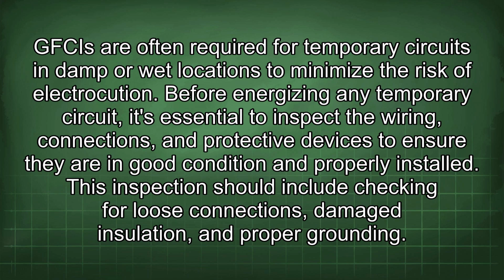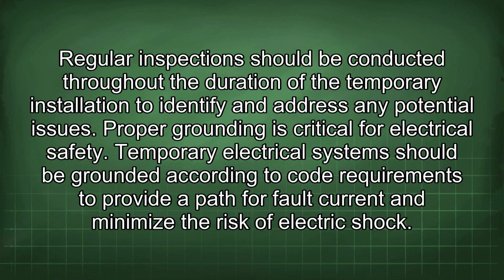Before energizing any temporary circuit, it's essential to inspect the wiring, connections, and protective devices to ensure they are in good condition and properly installed. This inspection should include checking for loose connections, damaged insulation, and proper grounding. Regular inspections should be conducted throughout the duration of the temporary installation to identify and address any potential issues.